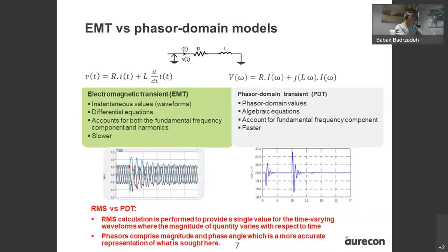This has to be done on an instantaneous basis. Looking again at this waveform, you can see the values are not the same. In steady state, whether you take t=1 second or 1.2 seconds, the values won't differ. But during the fault and after fault recovery, the values won't be the same at any given point in time. This is why the actual equipment needs to look at these individually and instantaneously.